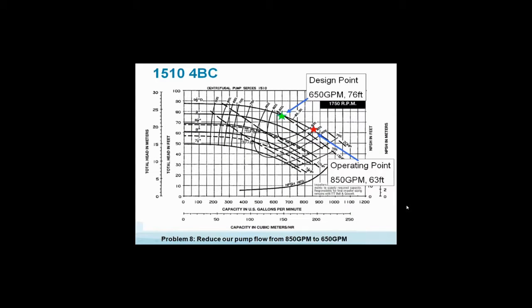Let's go back to my pump curve. That green star was the design, 650 GPM at 76 feet of head. Beautiful selection. My pump's not running there. Where is it running? It's running where the red star is. It hasn't been balanced. Nobody's done anything to it. We've got too much pump head. Where does it wind up running? Well, it says we have 63 feet of pressure drop across my pump.